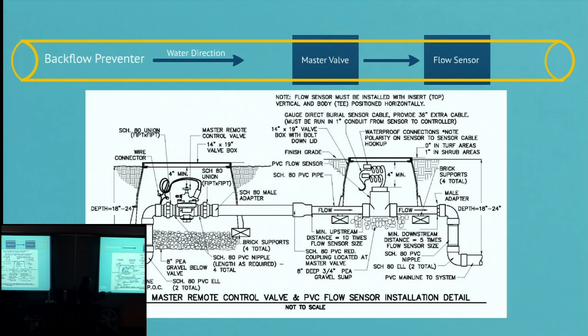This one has to be 10 times diameter, or the flow sensor diameter. This has to be 10 times that length with no fittings in it, and downstream it needs to be 5 times the diameter of the flow sensor. And the reason for that is that the water needs to be smoothed out so that the flow sensor is reading the gallonage correctly.